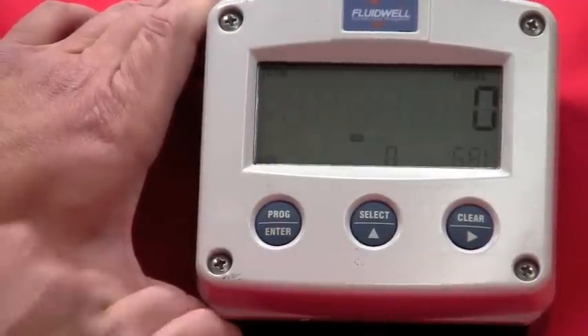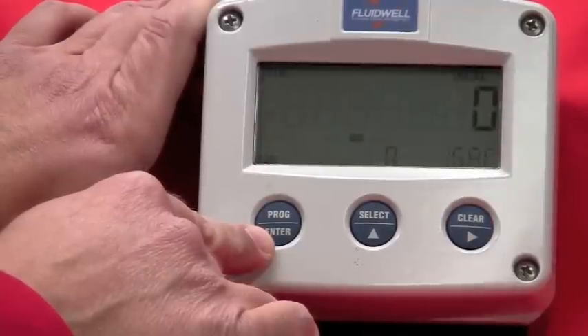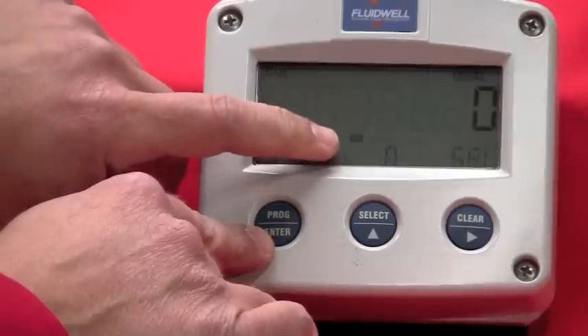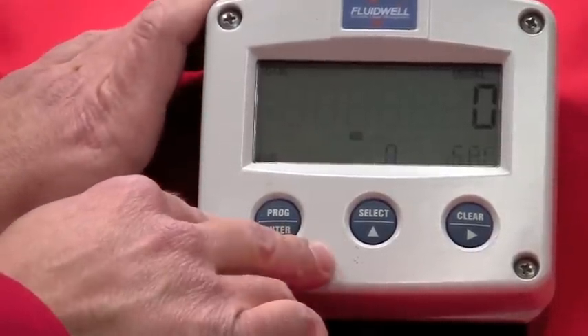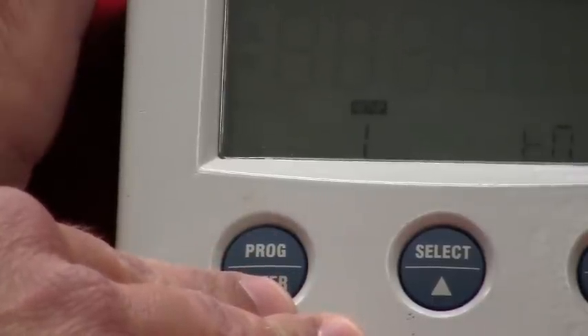Now, to get into programming the unit, we're going to use the program key, and I need to hold this button down for seven seconds to enter the programming mode. What you'll notice is the run mode will change to programming, and that will enable us to get into the menu structure of the meter. So I'm going to push this in and wait for seven seconds. And now we're into the programming mode of the meter.